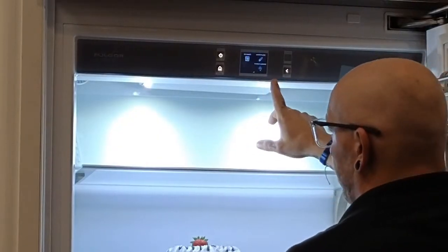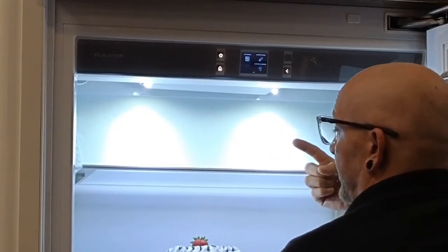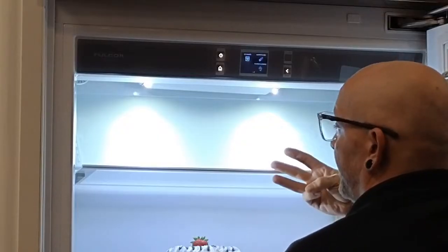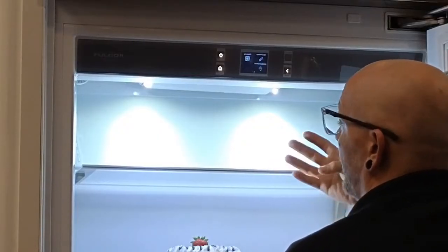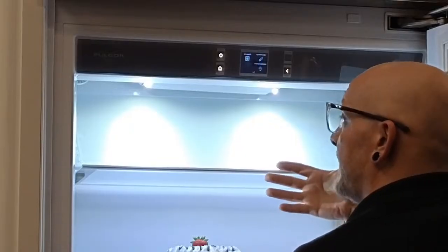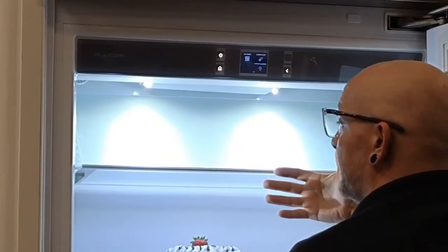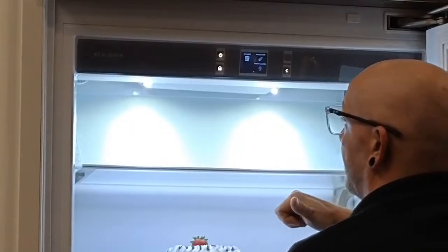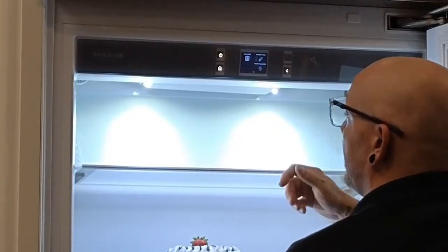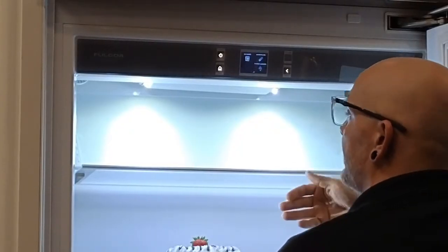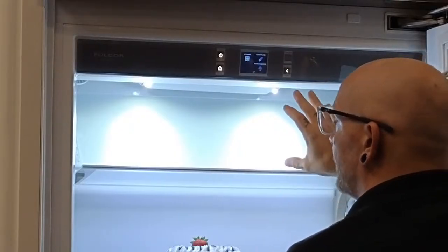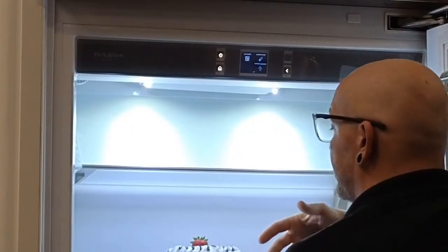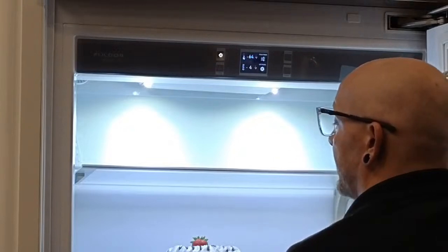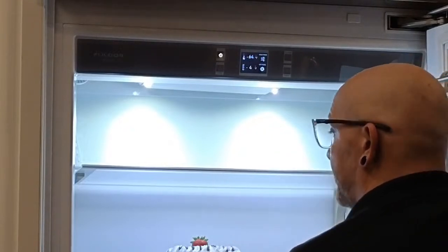So system cleaning, anything to check ice maker function, water function and water entering through the ice maker. You also have a fill tube heater that can come into play. If that heater fails, it may form an ice dam inside that fill tube and prevent it from filling. So there's other things to check, but this is a great tool and resource to at least pressurize the system, check communication between your electronics and your ice maker, and confirm that they can actually communicate.